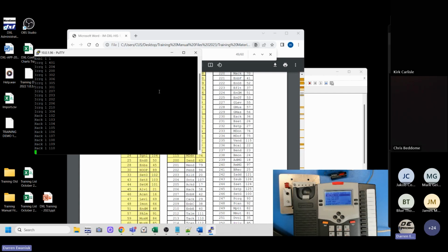there are two methods of getting information from the DXL system. You can either read registers from the DXL system, copy them and then act on them, or the DXL system can update you as activity happens. For a polled method, when you read a register, the intercom system assumes that you process it before you read the next one. So you read a register, and it makes the next register available. It's always when you read it that it puts the next command in, until you've cleared your backlog.